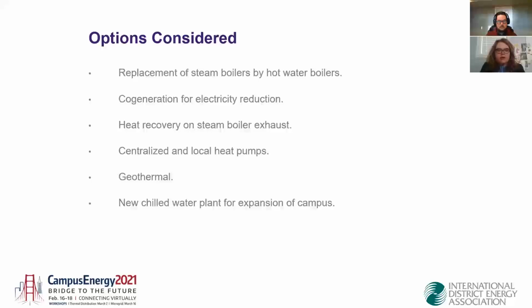There was the option of installing generators to have a cogeneration plant, or a cogen, to produce electricity and recover the waste heat to produce heating water. But again, because of the structure of the electricity cost, that option required a lot of capital investment for the savings that it generated, and there were GHG emissions related to that. There was the option of heat recovery on one of the steam boiler exhausts. So that was to recover heat from the boiler stack and use that heat for multiple uses in the plant and elsewhere on campus. There was the option of centralized or local heat pumps.